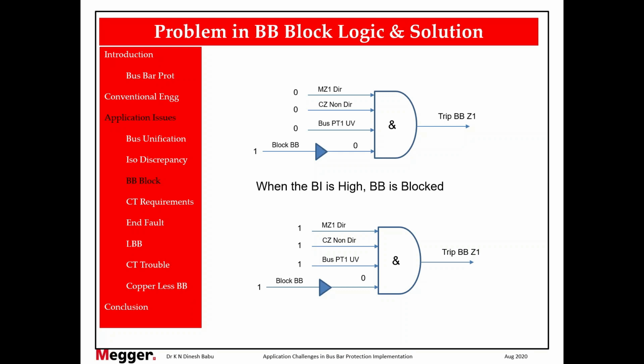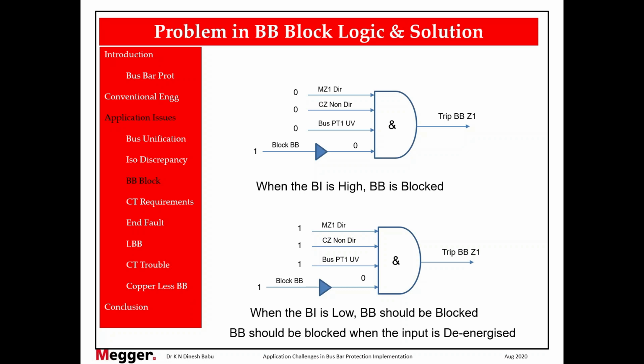So how to overcome this? Simple concept. When the binary input is low, bus bar should be blocked. That's all. So the very simple NOT gate is, whenever the binary input is high, we have to allow tripping. Whenever the binary input is low, we have to block tripping. So this NOT gate logic should be implemented in the schemes to ensure that this kind of problematic situation is addressed in a perfect manner. So bus bar should be blocked when the input is de-energized and not when the input is energized. So next one, CT requirements.